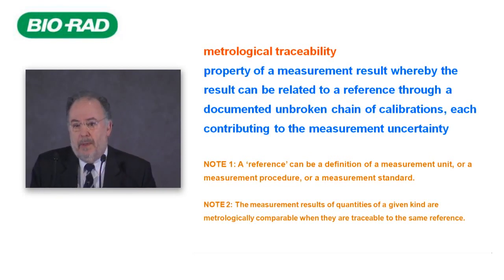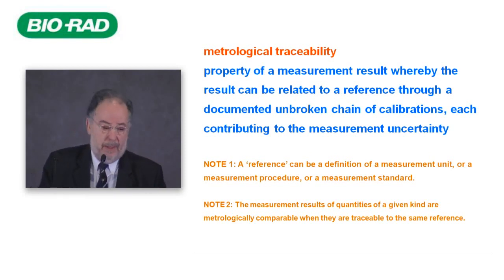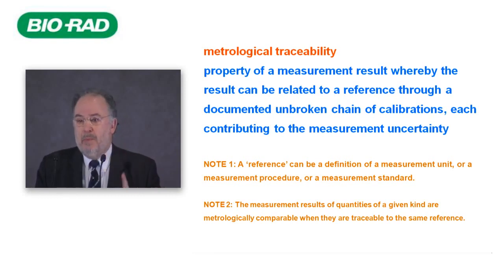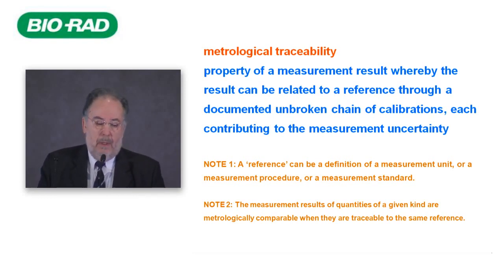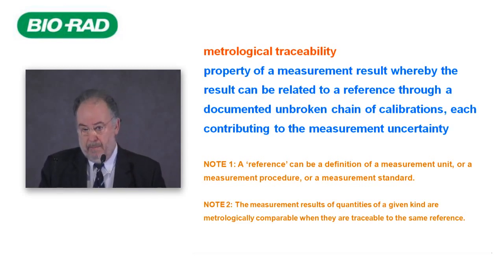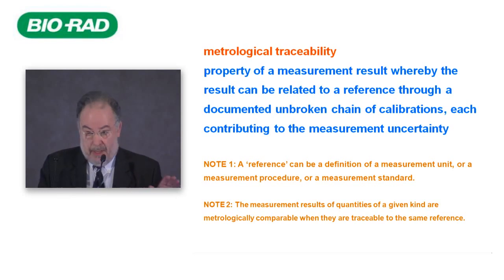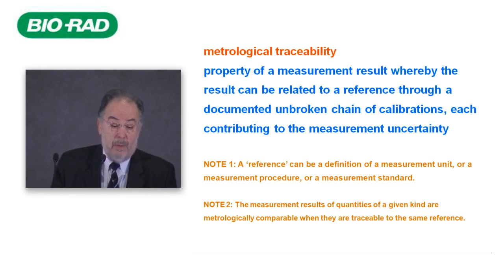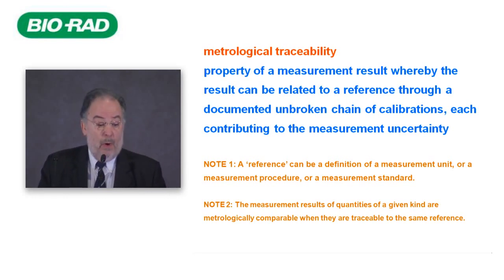The second very important concept is traceability. This is a metrological property of a measurement result. When traceability exists, the result can be related to a reference through a documented and unbroken chain of calibrations, with each calibration contributing to the measurement uncertainty. The reference can be a definition of a measurement unit, a measurement procedure, or a measurement standard.